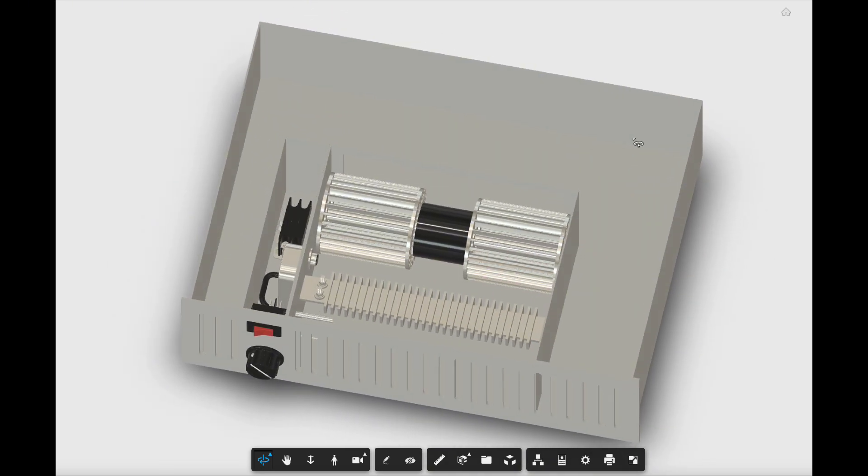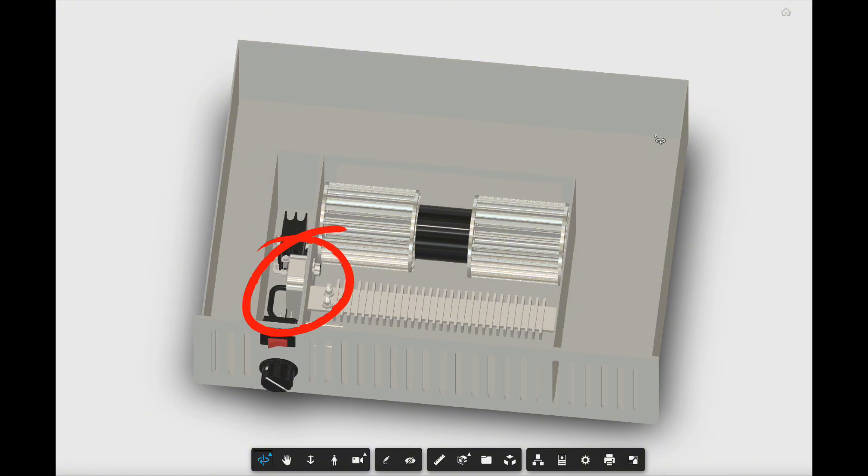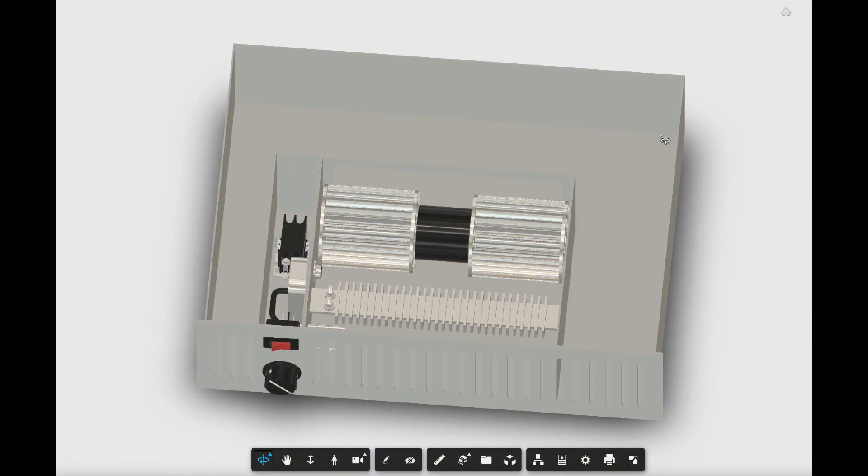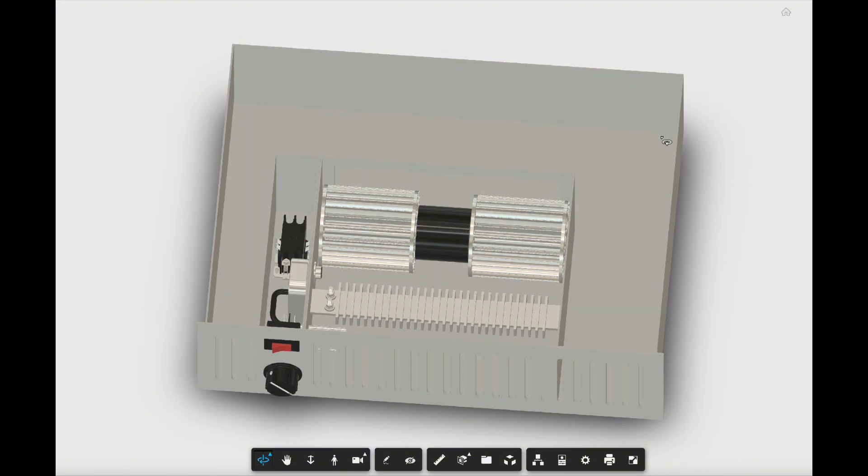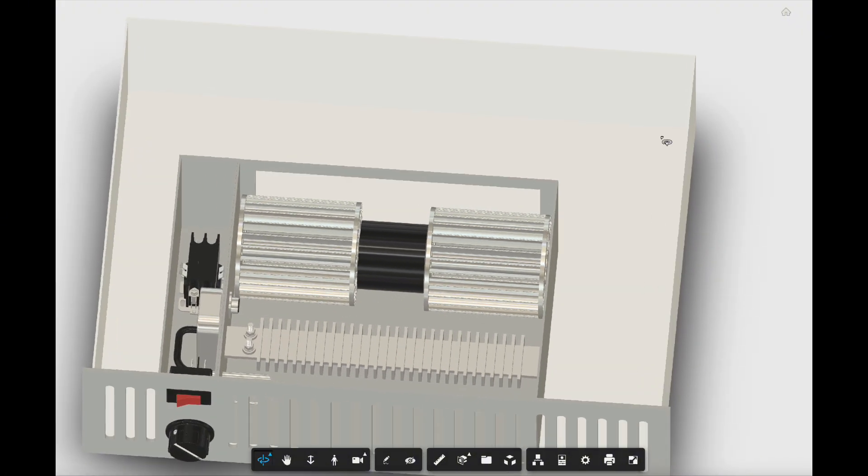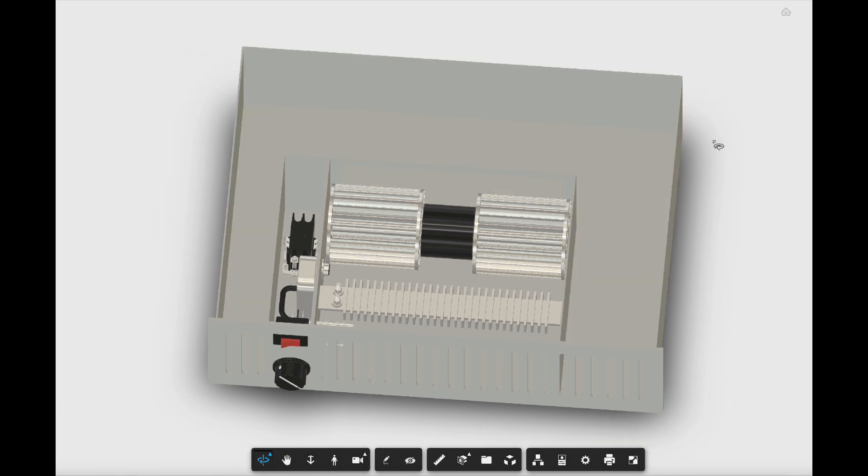You've got an air-proving switch. So the fan won't run, or excuse me, the electric heater won't kick on unless the fan is running. So that's the purpose of that air pressure switch. Then you've got a big contactor that will provide power to the electric heating elements.